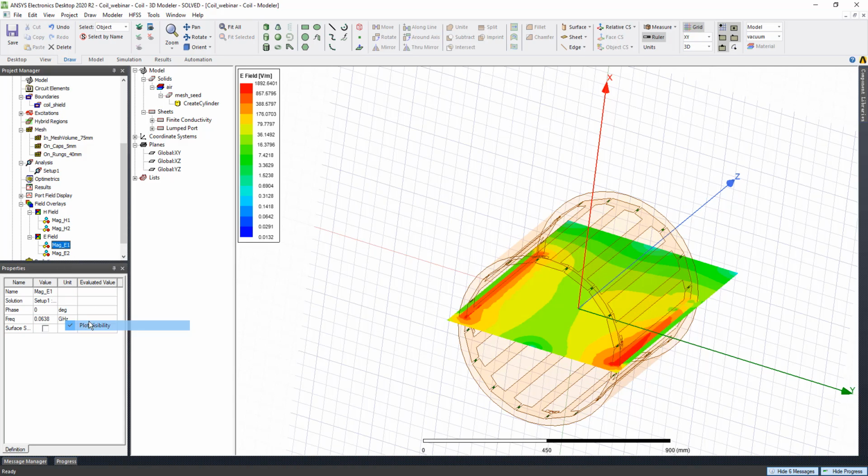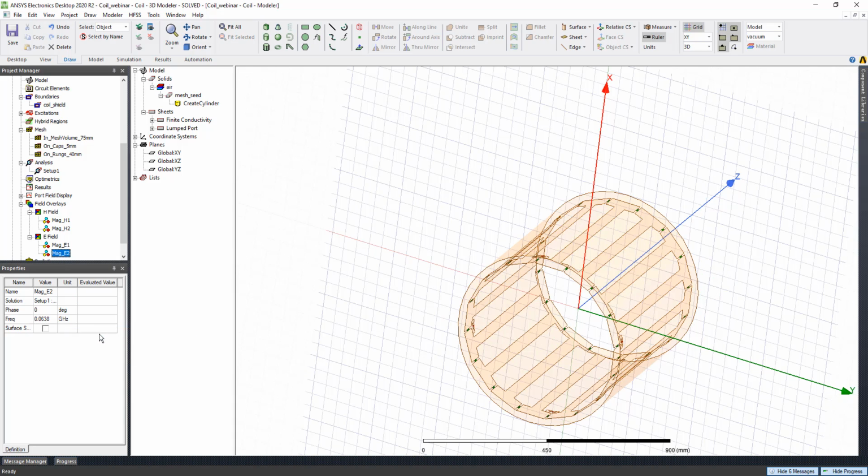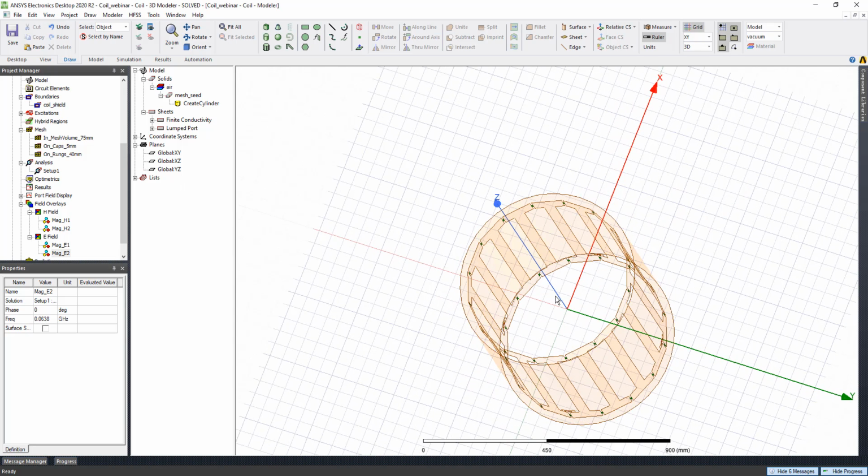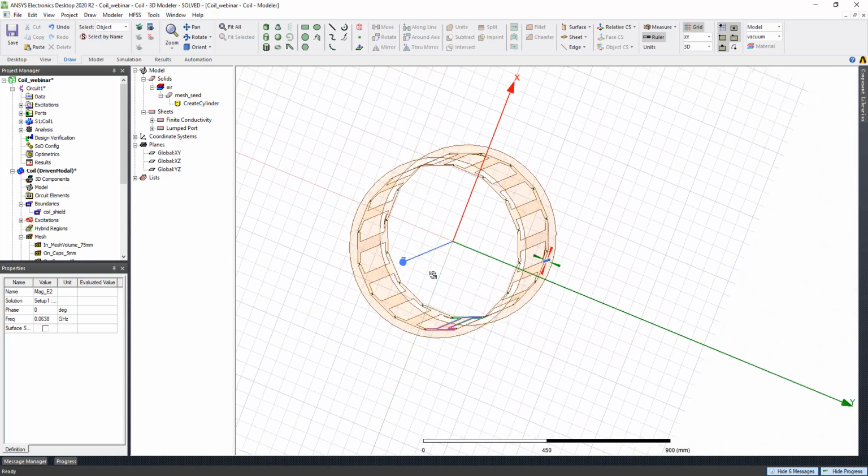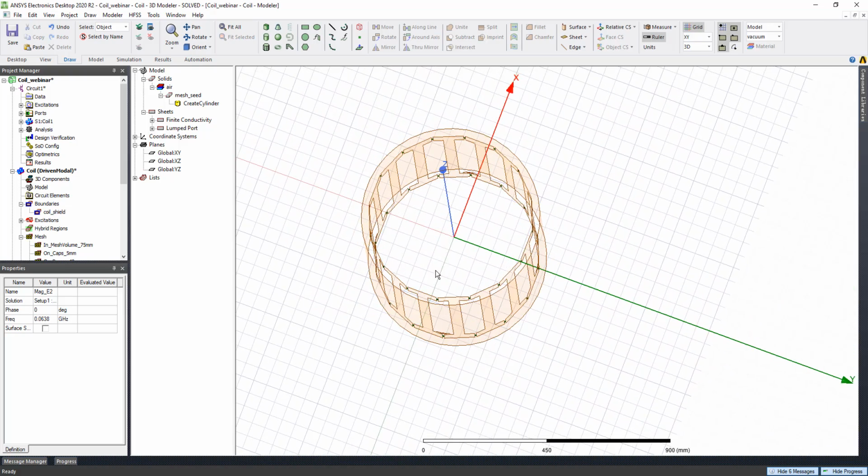Next, I'm going to bring in the gel so we can actually see the SAR value for this one. So to do that, the first step is of course to set up your MRI coils, have everything done like the field, and make sure your MRI coil meets the performance that you desire.